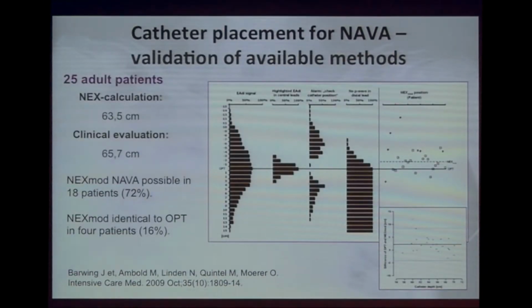So what you see here is the information we can derive, as I mentioned. You see the Eadi signal at different positions with regard to the optimal position. You see the highlighted Eadi signal in the mean, that should be in the mean electrodes, and then you have this alarm information and the no P-wave information. And if you compare all these variables which we took into this optimal positioning procedure to this NEX formula, as you see here, then we get the information that the NEX, of course, gives us a good estimate to place the catheter. As you see here, we end up with a median value of 63 centimeters.